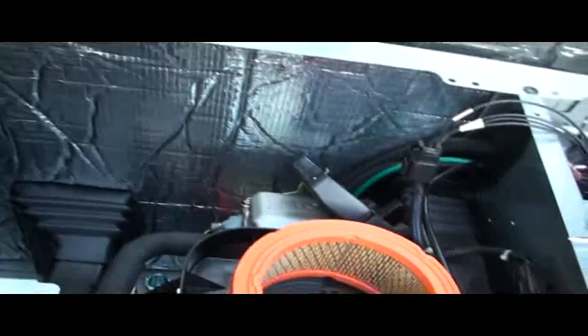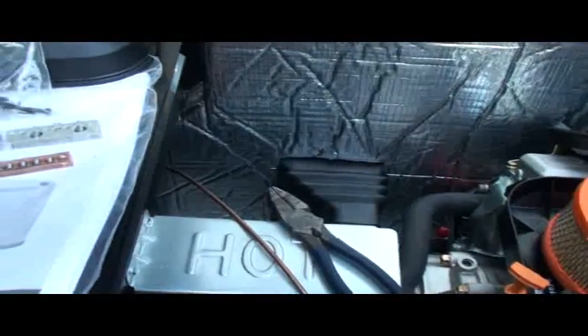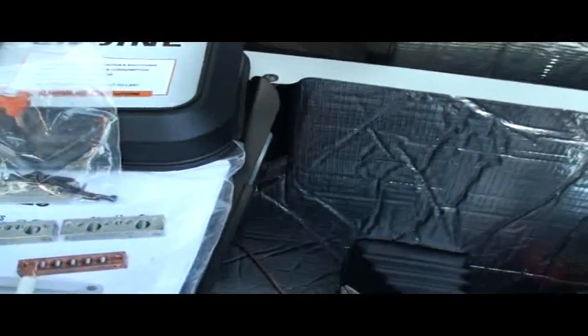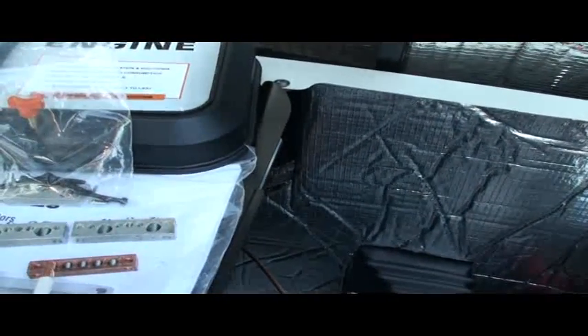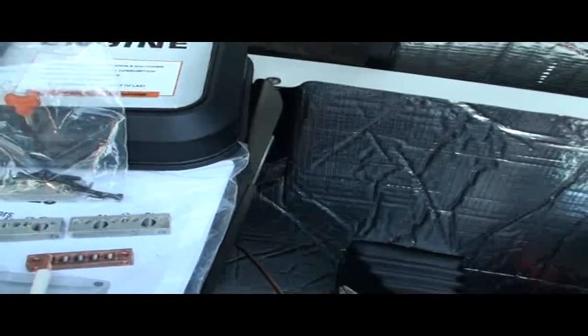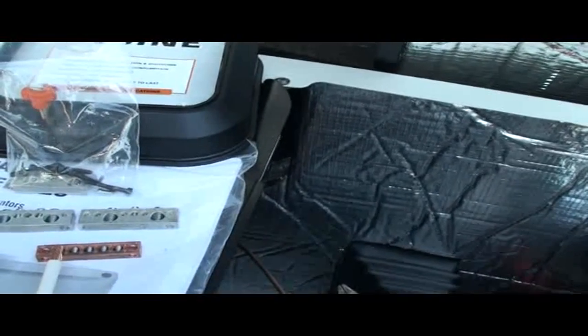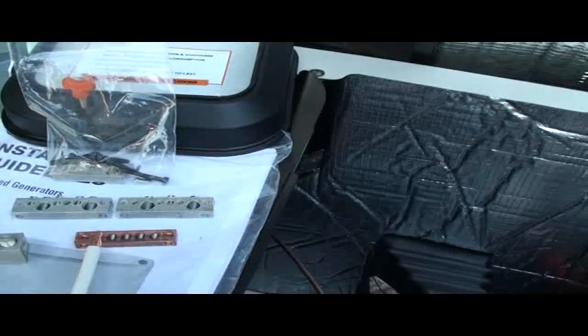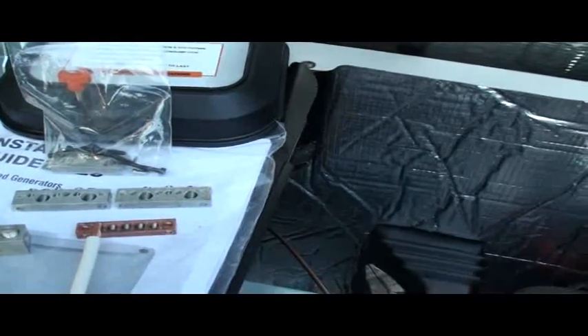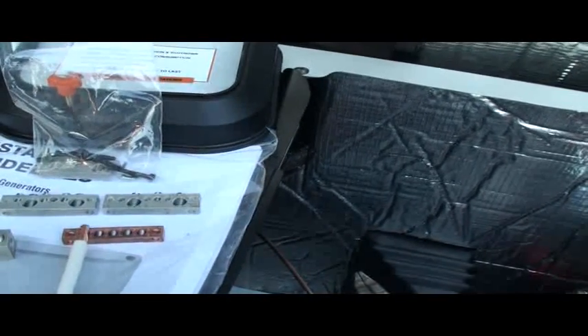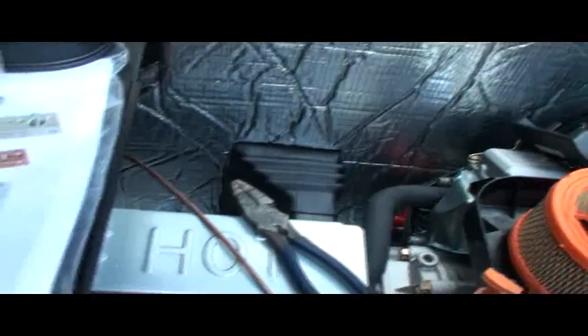But nobody's really going to run number four solid through conduit. It's not a very common thing to run number four solid through conduit. So here's a piece of number four stranded. Well, the stranded wire has a larger size, and as such, won't fit into the ground bar for the neutral or the ground. That presented me a problem.